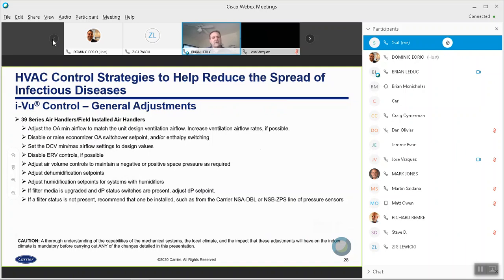Raise your OA switchover, your enthalpy switchover, set your DCV minimum, disable ERV controls if possible, adjust your air volume controls to maintain negative or positive if you're in an application that has, say, fan tracking, dehumidification adjustments, humidification adjustments, filter media, same guidance there.